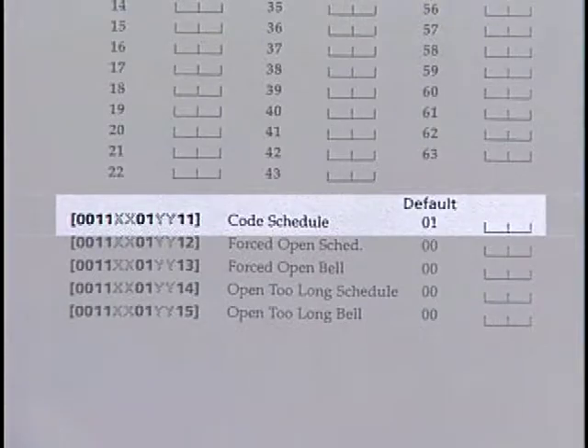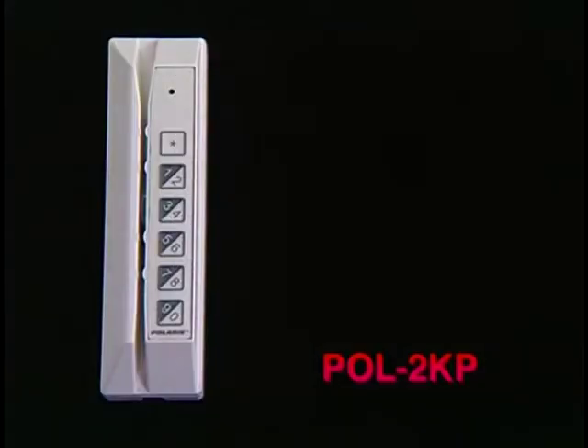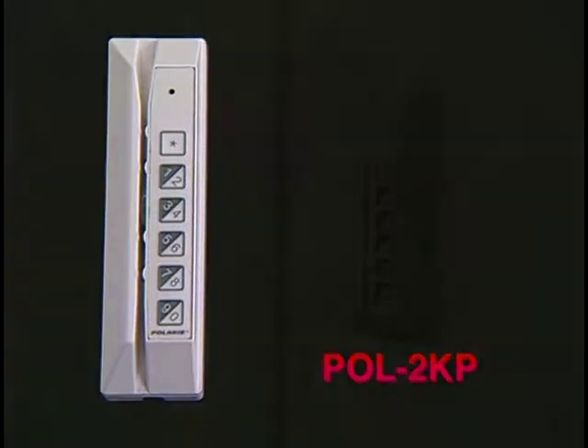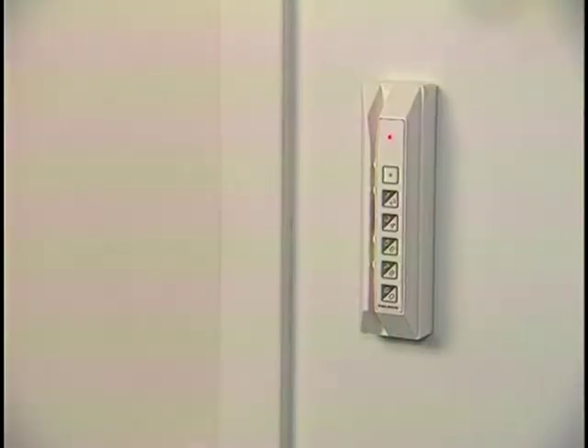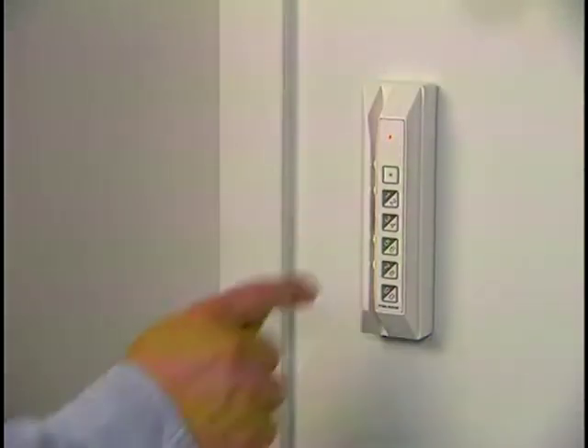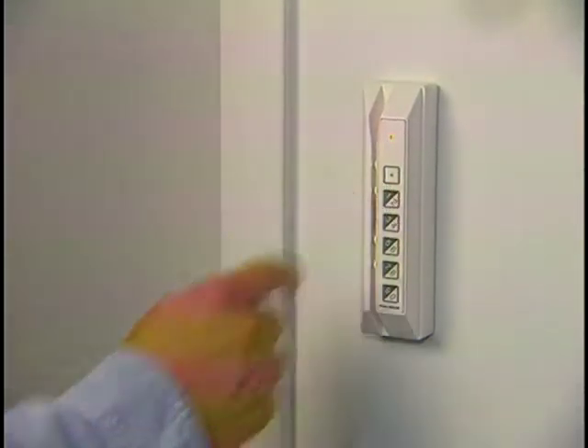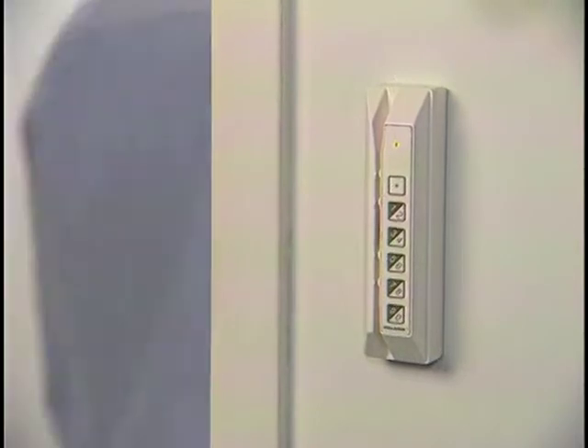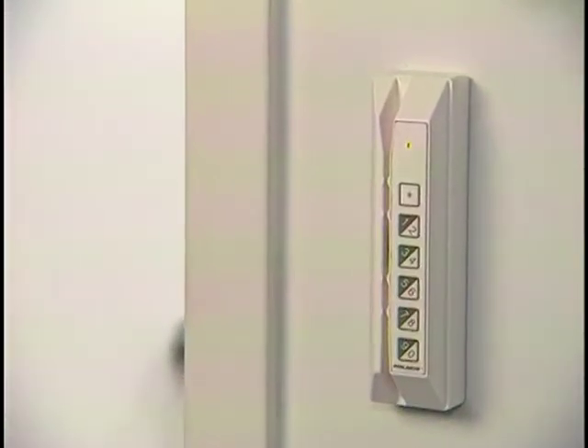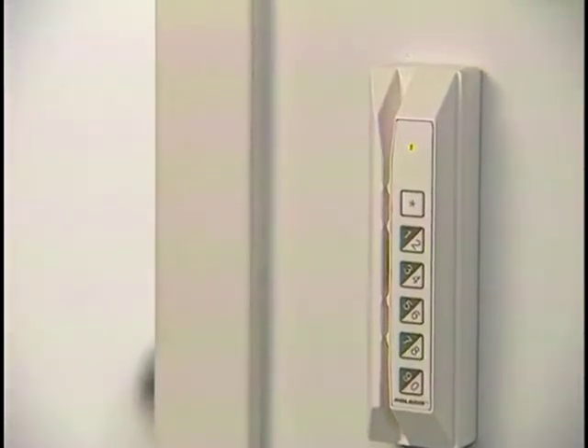Code schedule only applies if you are using either the POL-2KP Polaris reader, the Magstripe reader with a built-in keypad, or the HID PR5355KP reader with a built-in keypad. During the scheduled time, you will have to enter your 4-digit ARM/disarm code after presenting your card before the door will be released. Outside of the schedule, just presenting a card will release the door.